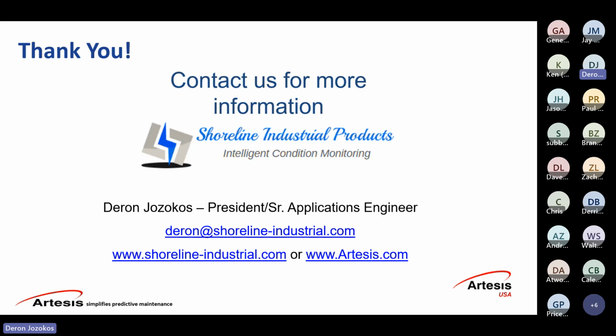Any benefit to connecting with a vibration monitor? Not sure exactly what you mean by that, but it is nice, of course, to still have a vibration portable data collector to maybe verify a fault. If the Artesis system you have says you have an imbalance, you would need the data collector to go balance the machine. So again, maybe just for verification and for some balancing, or you can do phase analysis to find looseness or structural looseness.